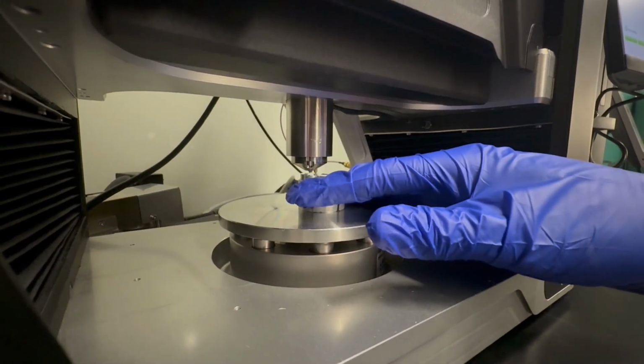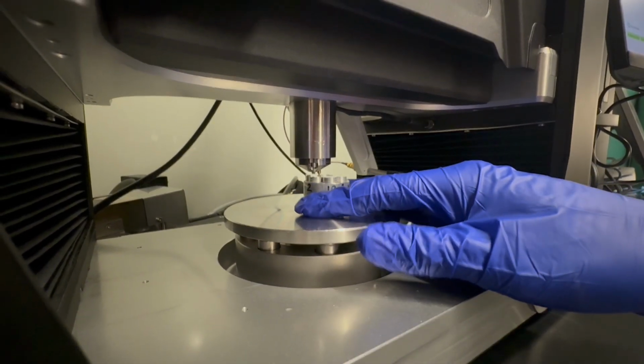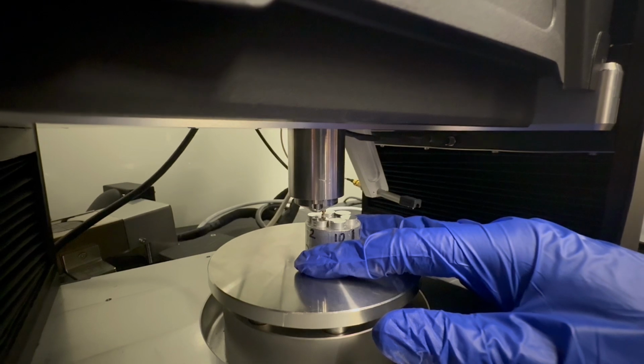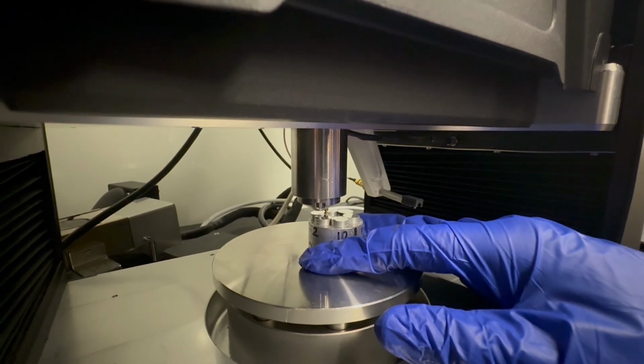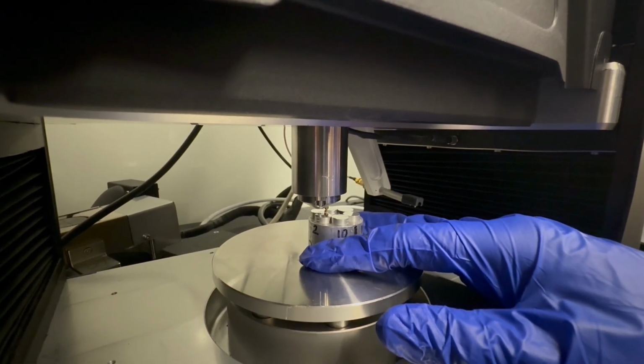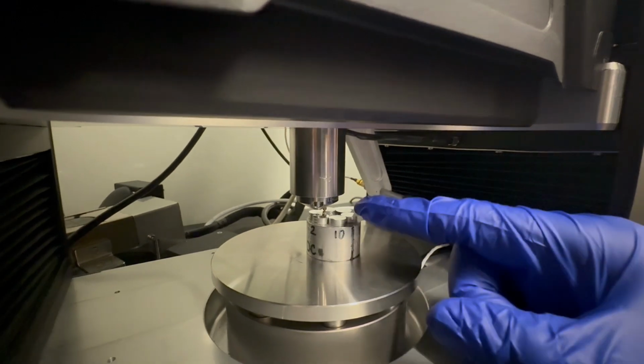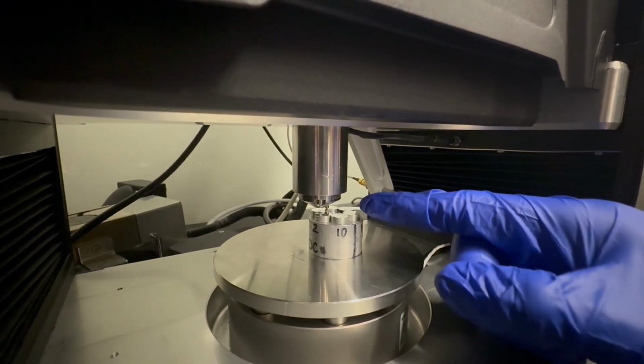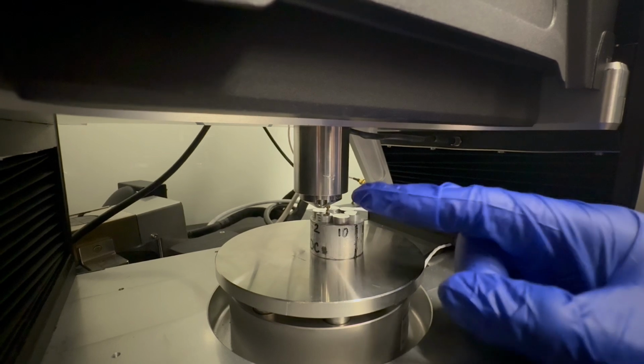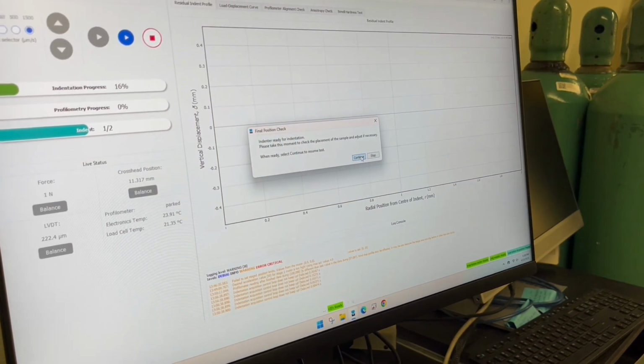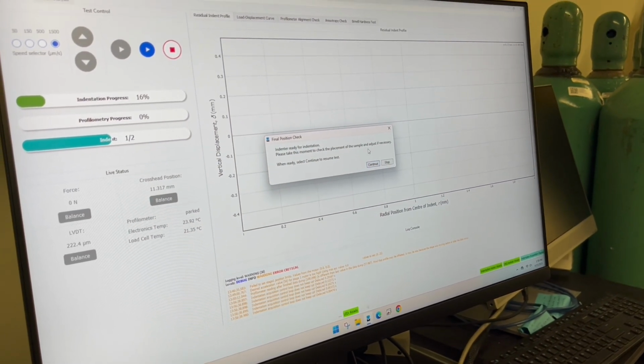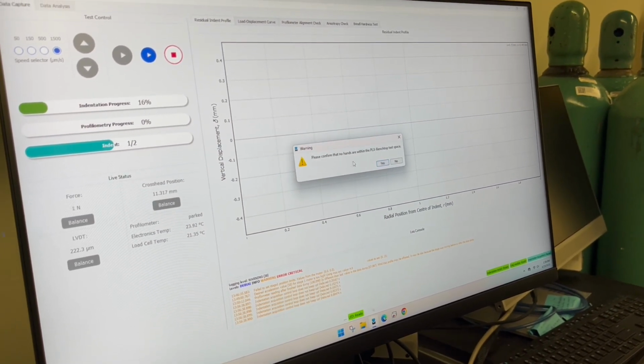Now you can adjust the sample so that the indenter tip is over the center of the sample you're trying to indent, making sure that the LVDT is still touching the top of the sample. For this part, you want to ensure that the indenter tip is going to be 3 millimeters from the edges and 6 millimeters from any other indents. You also need to make sure that the sample you're indenting is at least 3 millimeters thick. Now that you've completed the final position check, you're ready to continue with the indentation.